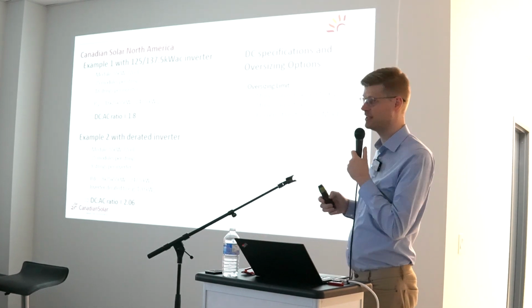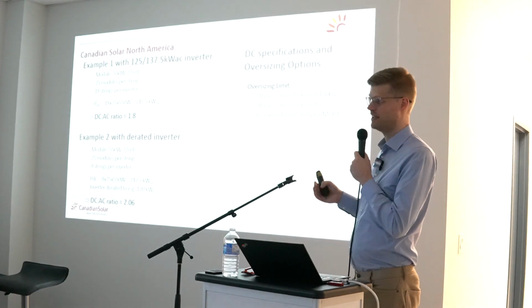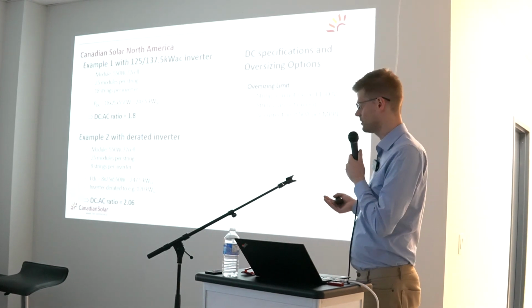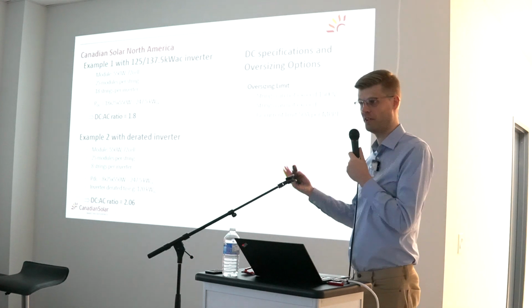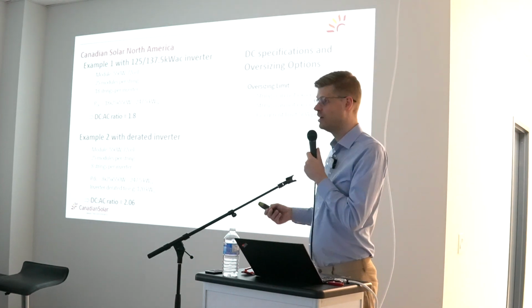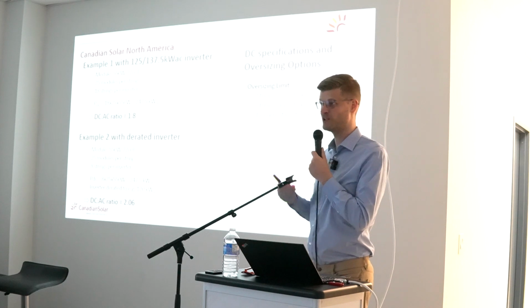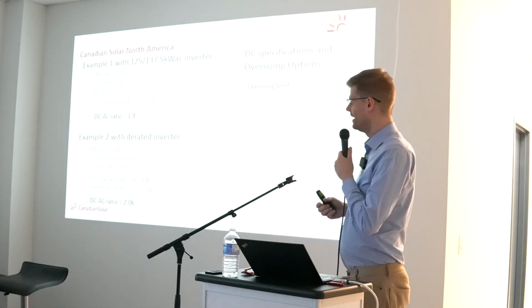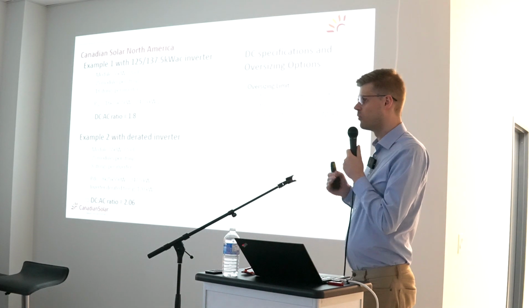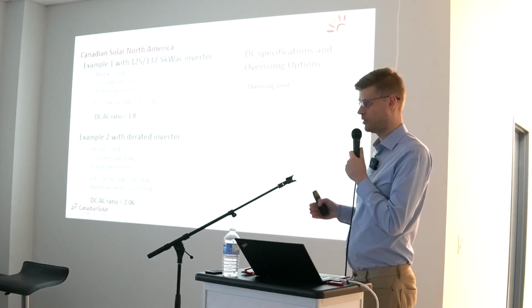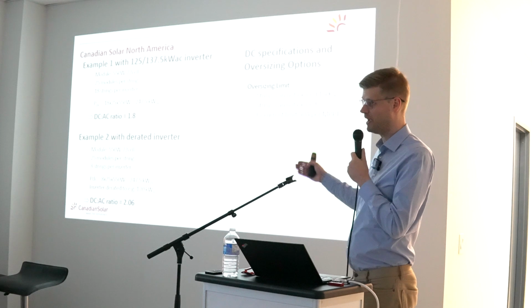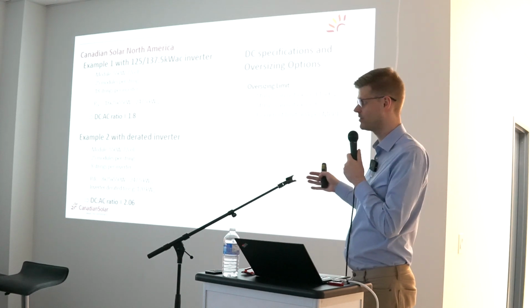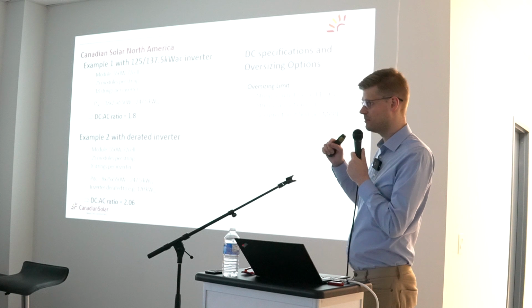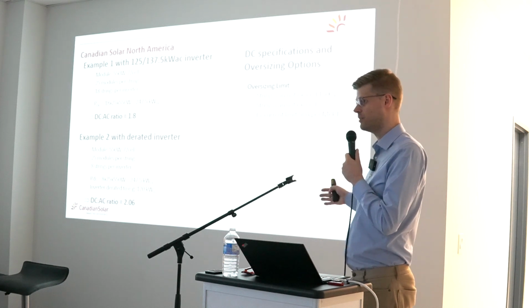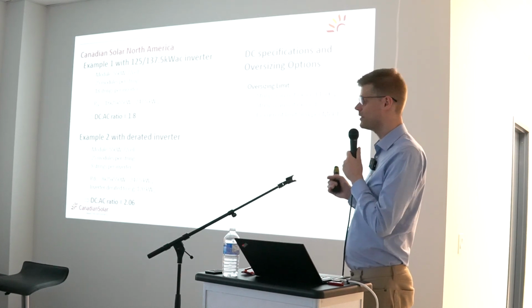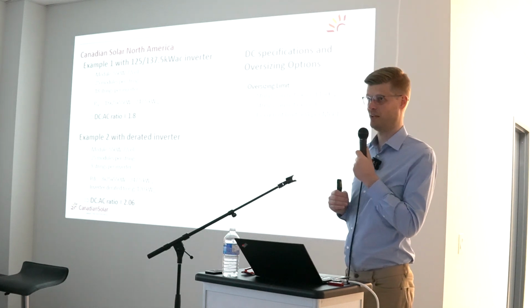That's one option. The other option is, for commercial rooftops these days and the service connections customers are having, for example, we have here a 400 amp electrical service at 600 volt. You only have a certain capacity based on your busbar rating and your service size. And you probably don't want to rip out your entire service and put a new electrical panel in with higher busbar rating and then be able to add another inverter or maybe just a few kilowatts more. You want to keep the system all the way to your main breaker and your connection as cost effective as possible. And that typically means that you don't want to change an existing electrical service.